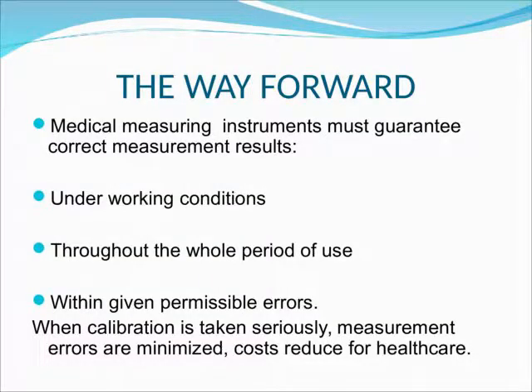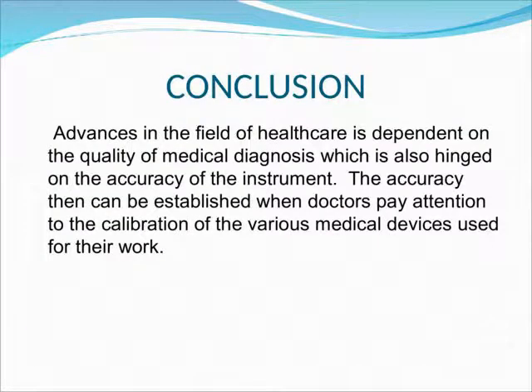So on this note, what I'll say is that the measuring instruments, or weighing instruments for that matter, must at all times work very well throughout the whole period of use, within the permissible error. And once we can achieve that through calibration, it will even help us plan better. Once you do the calibration, even 1 or 2 years before the instrument goes off, you can tell from the previous records. So nothing will surprise you.